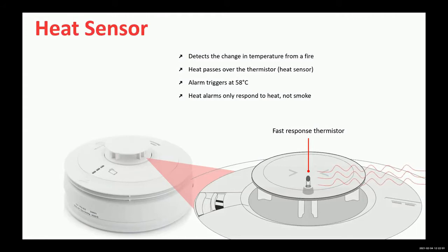It's more than likely that the customer, the tenant that's in the kitchen, has had something happen within the oven or the grill or whatever it is, and set the ionization detector that's outside the kitchen door into alarm. And the fact that they're all interconnected, the unit that they're standing under is the one that they think is after activating the system. But I can guarantee you, they wouldn't be standing in the kitchen if there was 58 degrees underneath that. So it's more than likely not the heat alarm that reacts to that. It's something that's triggered elsewhere. But the fact that they're all interconnected, as I say, would give that impression to the ordinary tenant, the ordinary person that's not au fait with the system.